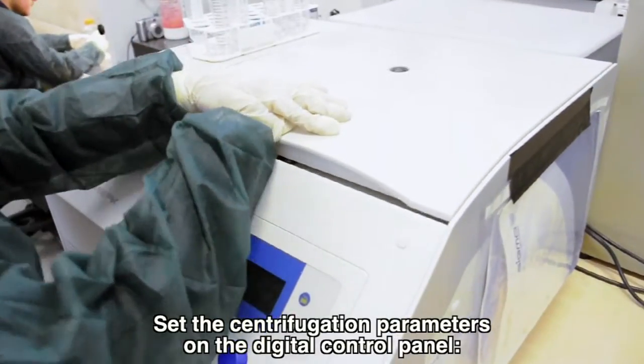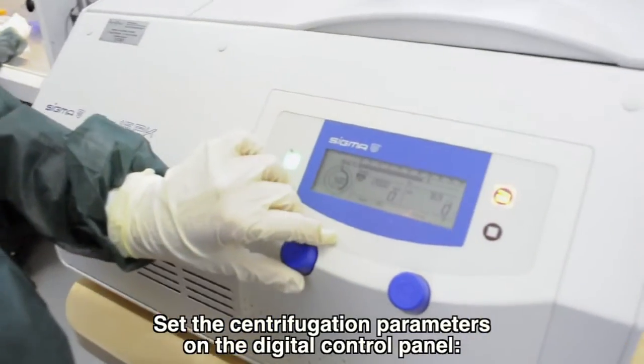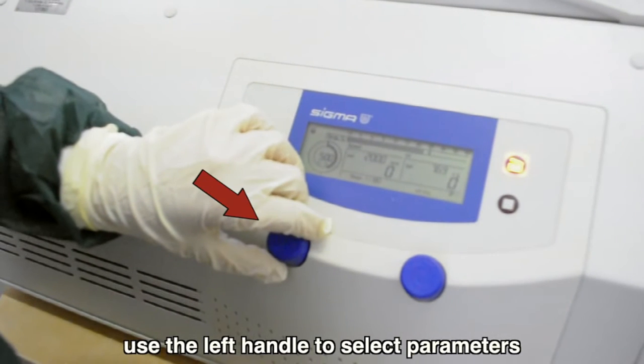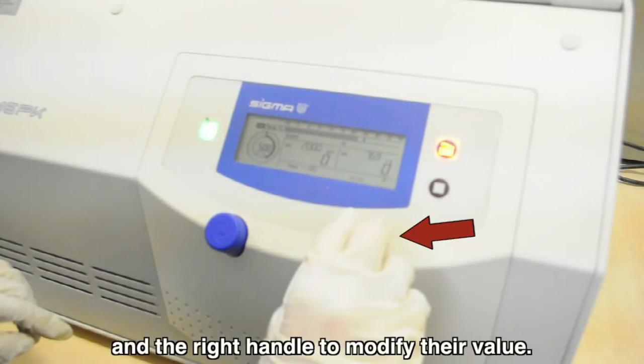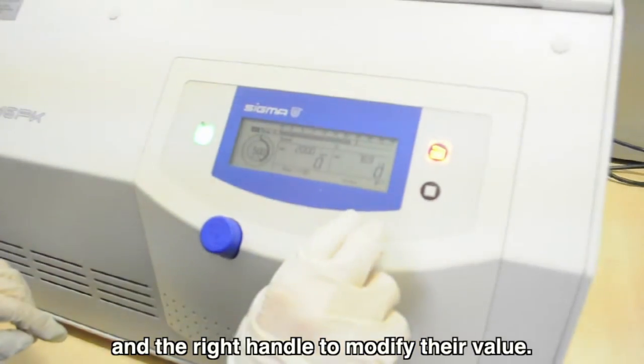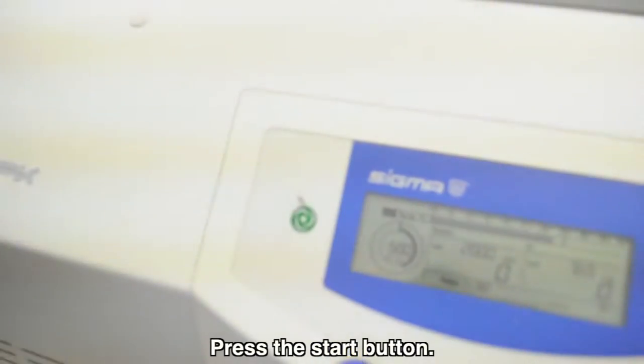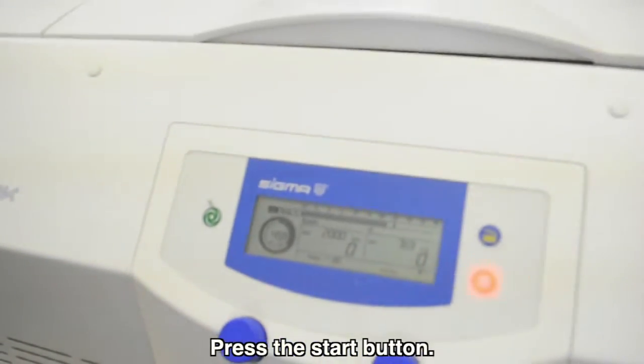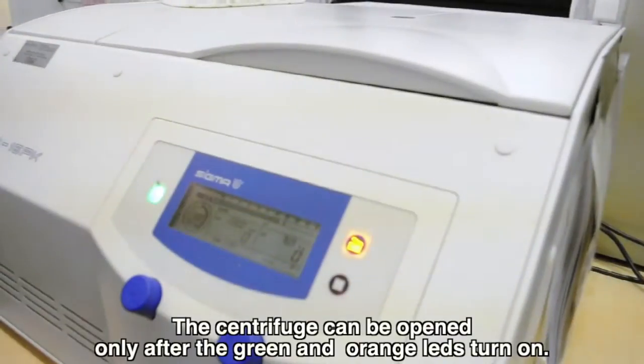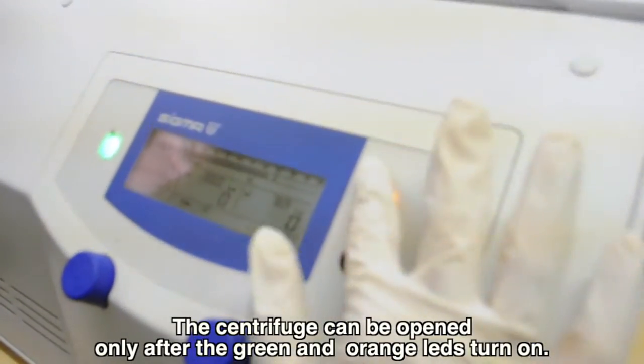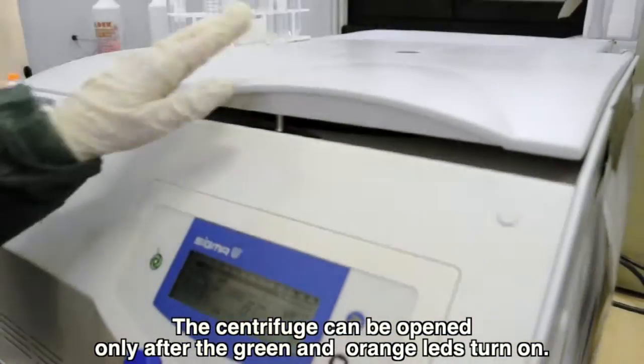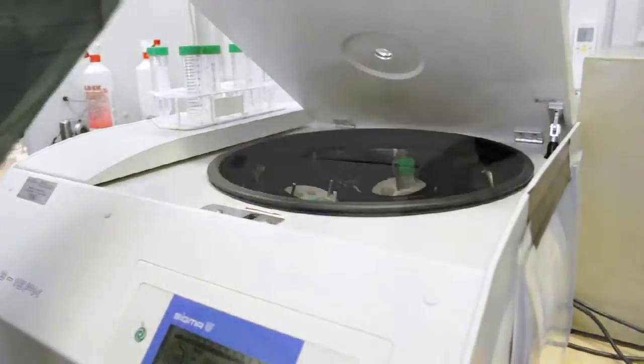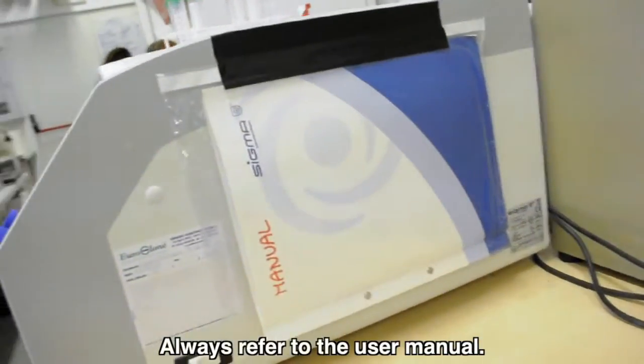Set the centrifugation parameters on the digital control panel. Use the left handle to select parameters and the right handle to modify their value. Press the Start button. The centrifuge can be opened only after the green and orange LEDs turn on. Always refer to the user manual.